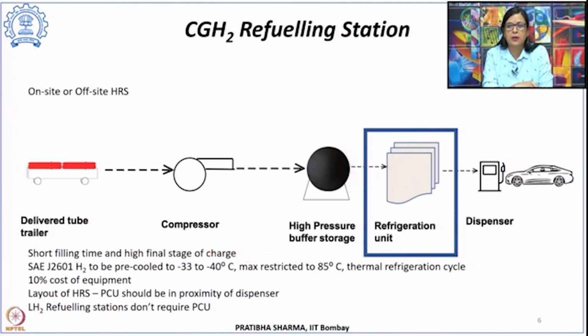Now as per the SAE J2601 standard, the hydrogen before filling should be pre-cooled to a temperature of -33 to -40 degrees centigrade. This is required such that the maximum temperature which could be reached during filling is 85 degrees centigrade. So that is the maximum restriction on the temperature achieved during the filling process, and this refrigeration is achieved through a thermal refrigeration cycle.